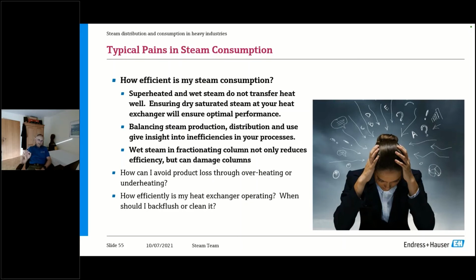However, true dry steam does not exist. This 100% exactly is really like reaching the sharp edge of a knife. Imagine a steam distribution line. You keep distributing the steam and you're losing energy. First it's superheated. You may still have maybe 5 degrees C of superheat, then you're losing more energy. You have 4, 3, 2, 1, 0 superheat. You're exactly at the saturation line, but that's for a microsecond. In the next moment, you have already lost more energy and you are in the wet zone. So there is no saturated steam. In reality, there's only wet steam or superheated steam. This is very important. This is again why these outputs of the degrees of superheat and of the dryness fraction of the vortex meter are so important.